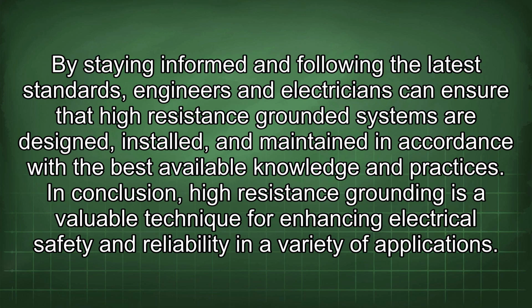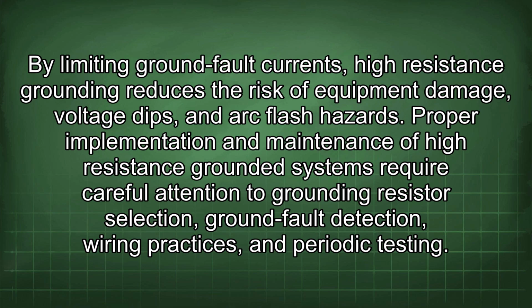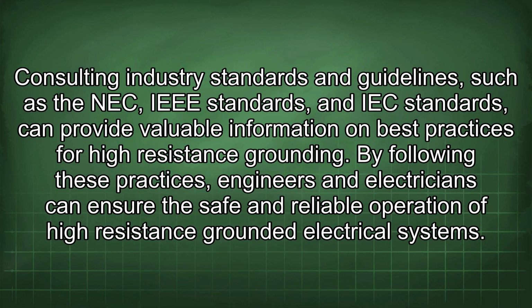In conclusion, high-resistance grounding is a valuable technique for enhancing electrical safety and reliability in a variety of applications. By limiting ground fault currents, high-resistance grounding reduces the risk of equipment damage, voltage dips, and arc flash hazards. Proper implementation and maintenance of high-resistance grounded systems require careful attention to grounding resistor selection, ground fault detection, wiring practices, and periodic testing. Consulting industry standards and guidelines such as the NEC, IEEE standards, and IEC standards can provide valuable information on best practices for high-resistance grounding. By following these practices, engineers and electricians can ensure the safe and reliable operation of high-resistance grounded electrical systems.